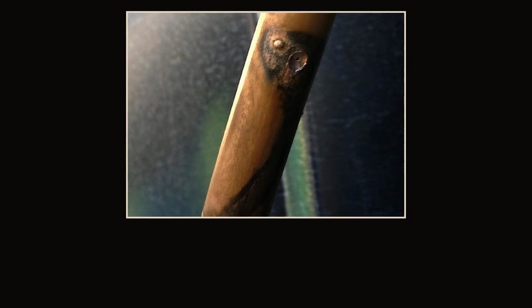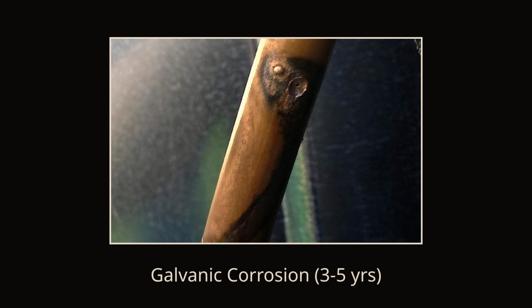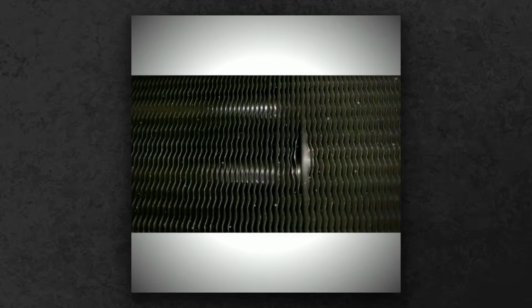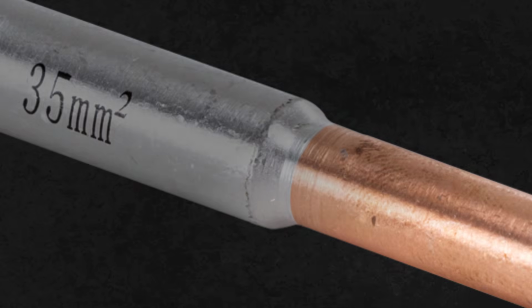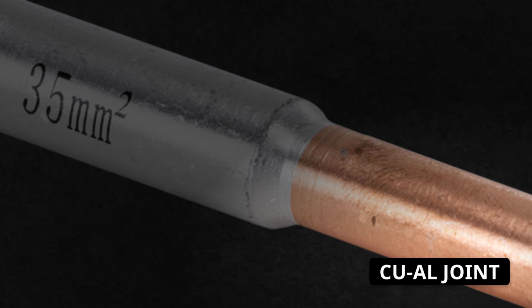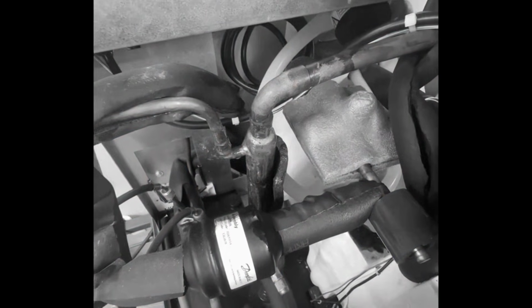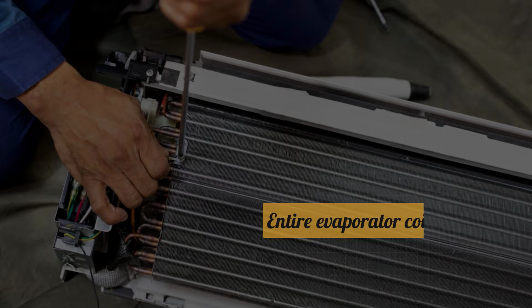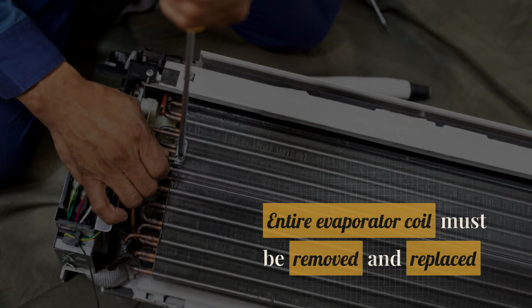When two dissimilar metals sit in a warm, humid, slightly acidic environment, which is exactly what exists inside an operating air handler, a chemical reaction called galvanic corrosion attacks the junction points from the inside out. Over 3 to 5 years, microscopic pinholes form at every copper to aluminum joint. Refrigerant starts leaking. Your system loses cooling capacity slowly enough that you blame the summer heat, not the machine. By the time a technician confirms the leak with an electronic detector, the entire evaporator coil needs replacement.